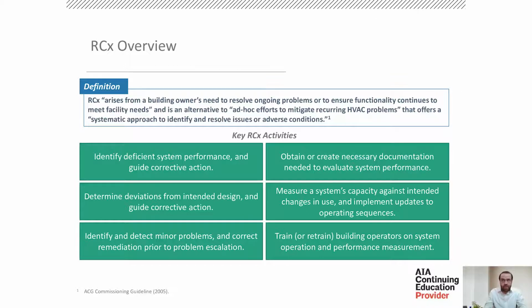Because of changes in the environment, facilities have to operate differently than when they were originally designed, and the commissioning agent will often come in front of the design engineer, the professional engineers, to recommend those changes and determine how to implement them. You're then back-checking those changes against the codes and designs to make sure it checks those boxes. But ultimately, it's an operational change that the retro-commissioning agent is working on to meet the intent of where a facility needs to be.